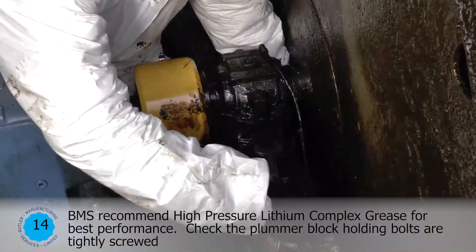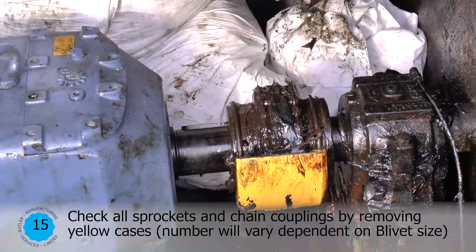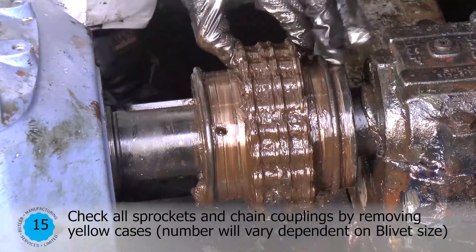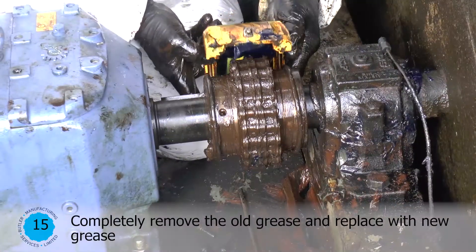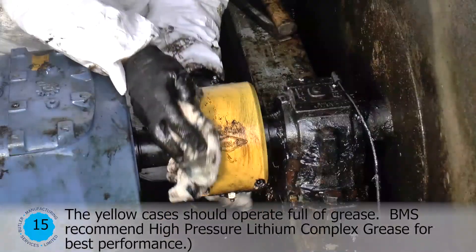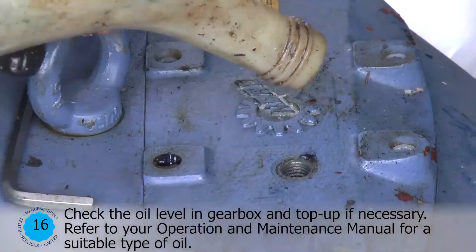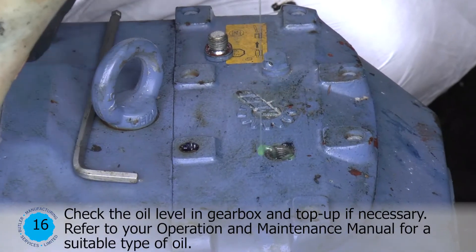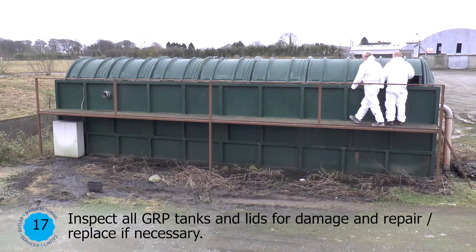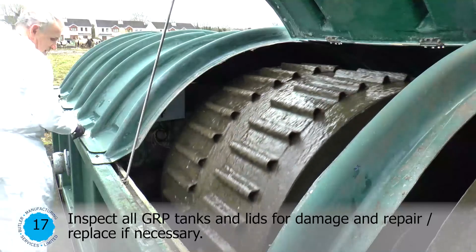Check the plummer block holding bolts are tightly screwed. Check all sprockets and chain couplings by removing yellow cases — number will vary depending on blivet size. Completely remove the old grease and replace with new grease. The yellow cases should operate full of grease. BMS recommend high pressure lithium complex grease for best performance. Check the oil level in the gearbox and top up if necessary — refer to your operation and maintenance manual for a suitable type of oil. Inspect all GRP tanks and lids for damage and repair or replace if necessary.